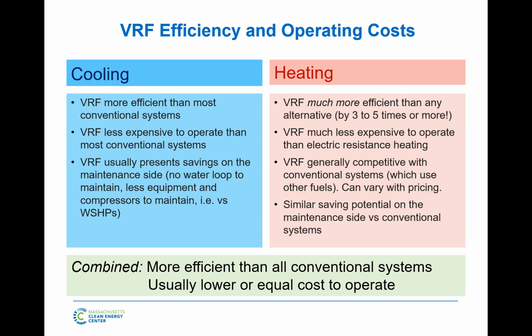Now on the maintenance side, we don't talk about this too much today. We can answer questions about it. Maintenance is usually one of our talking points with VRF. It depends what you're comparing it to. If you're comparing it to water source heat pumps, there's a big discussion about you don't have 100 compressors that are in your spaces everywhere in the heat pumps. We have 4 compressors up on the roof. There's a maintenance advantage there, reliability and all that.